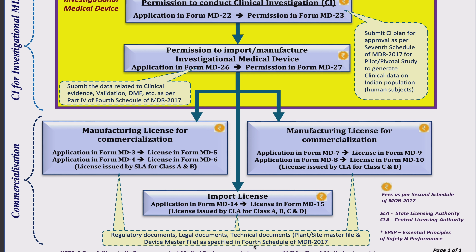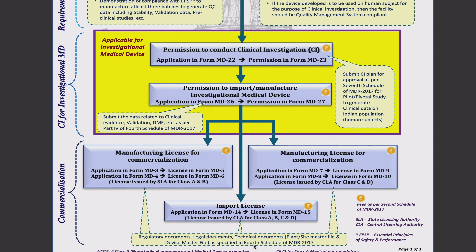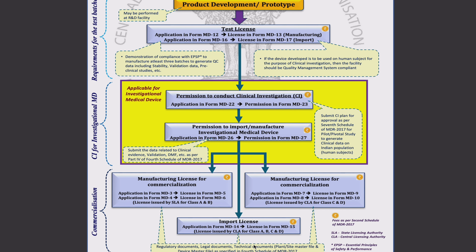To summarize, this was the regulatory pathway. First, once the product is developed, produce three test batches. Then move to the second phase — if it is an investigational medical device, follow the clinical investigation regulations; otherwise, move directly to the third phase, which is commercialization. Depending on the classification, file the appropriate application form. For import-only purposes, go straight to the commercialization phase by filing MD14.